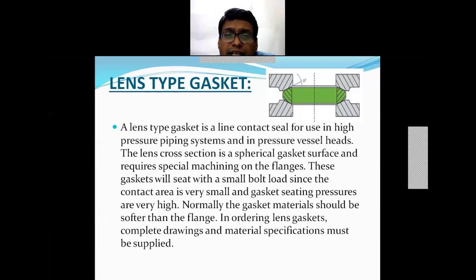Then the lens type gasket that is there. Lens type gaskets is a line contact seal for the use in a high pressure piping system and in pressure vessel heads. This lens cross section is a spherical gasket surface and requires the special machining of the flanges.